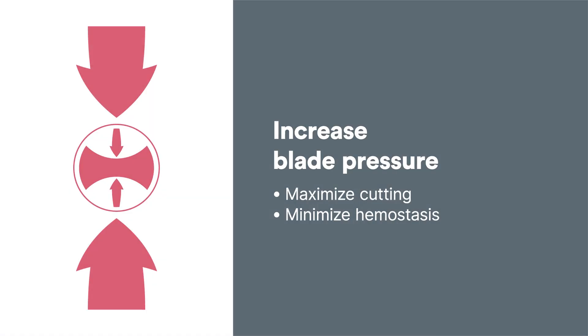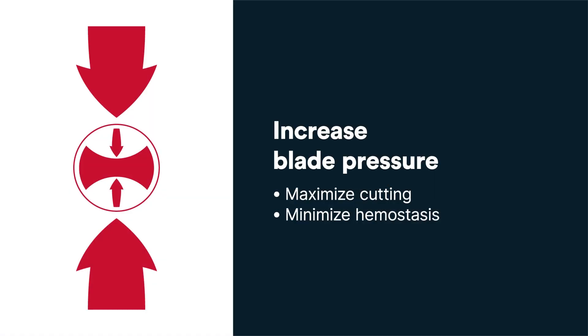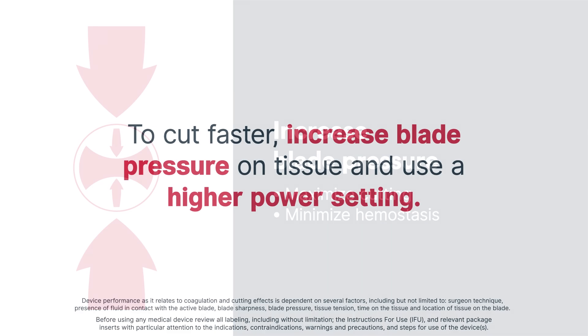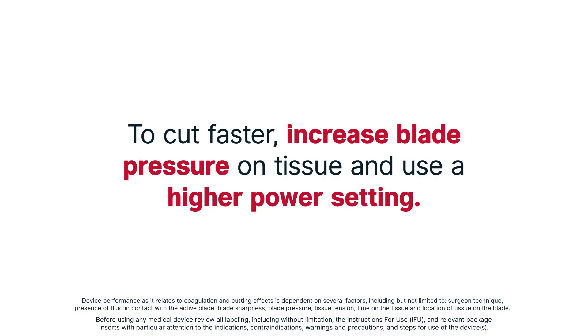Blade pressure. Increasing blade pressure on tissue will maximize cutting and minimize hemostasis. A surgeon wishing to cut faster should increase blade pressure on tissue and use a higher power setting. This is a common approach when dissecting or marching through tissue quickly.